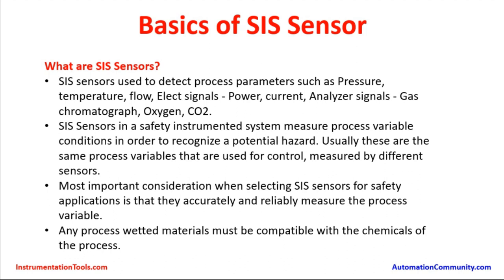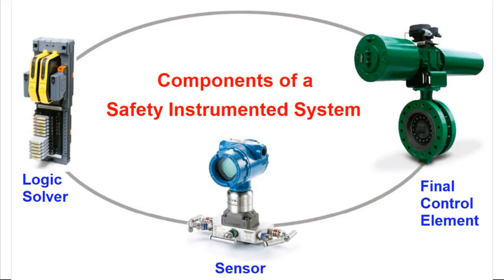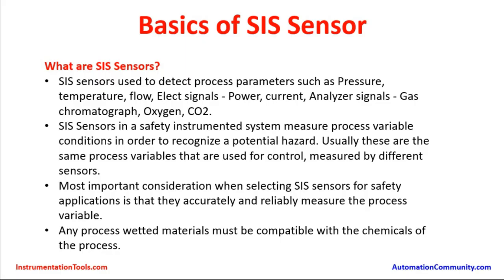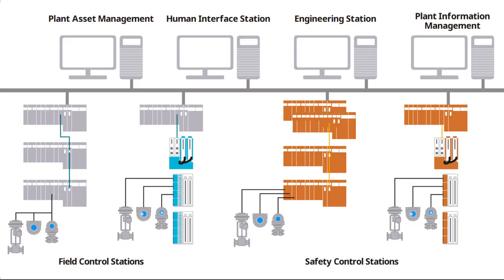SIS sensors in a Safety Instrumented System measure process variable conditions in order to recognize a potential hazard. Usually these are the same process variables used for control, but measured by different sensors. In the process piping or equipment, there are multiple sensors — one set for control applications, while the SIS sensors are in the same location but measured by a different set of sensors.